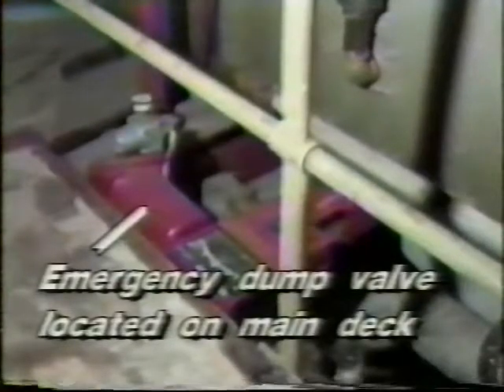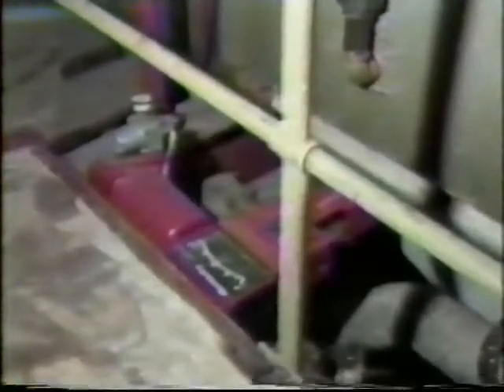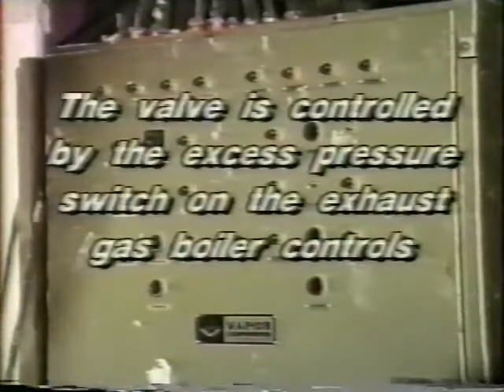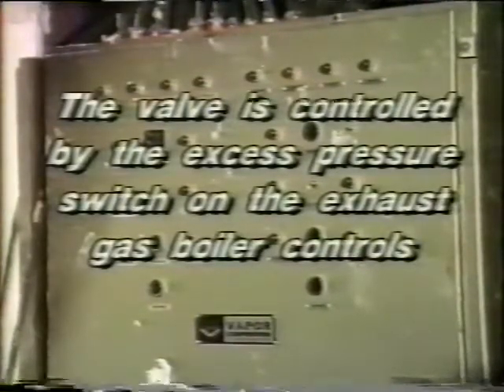In the event that the steam unloading system is not operating correctly, the exhaust boiler is protected by an emergency dump valve which is activated by a signal from the ship's control system. The steam from the emergency dump valve is piped to the atmosphere. This valve is controlled by the excess pressure switch on the exhaust gas boiler control.